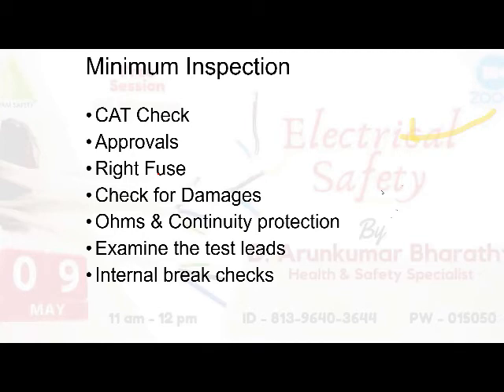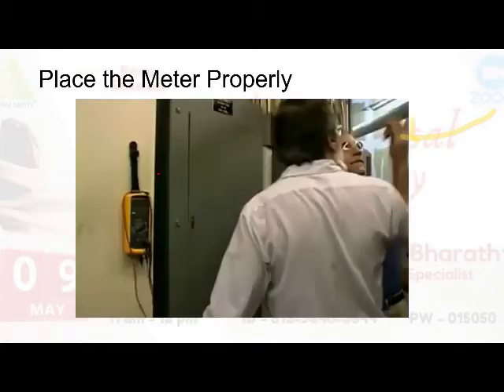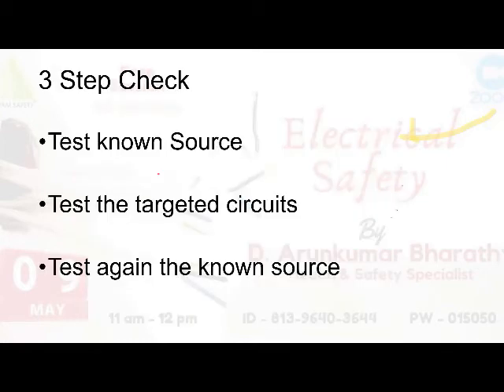What is the other suggested practice? Don't hold the measuring instrument in your hand. Why? If the instrument fails, that failure may cause electrocution. So always place the multimeter on a wall, or you can use a magnetic stick. This is fundamental, but most people are not following it.